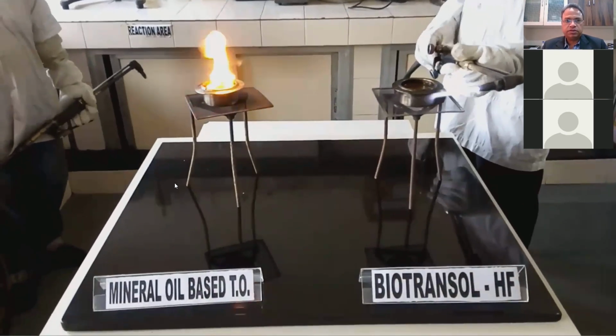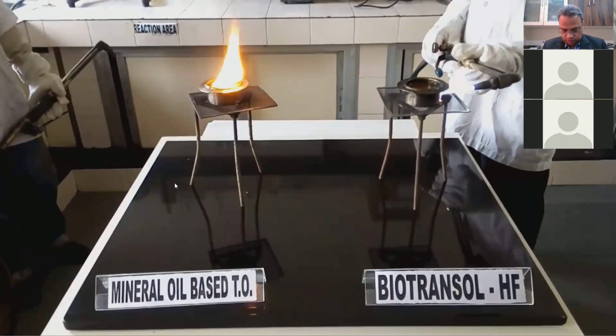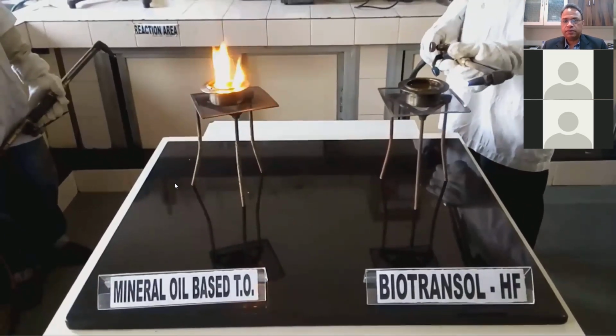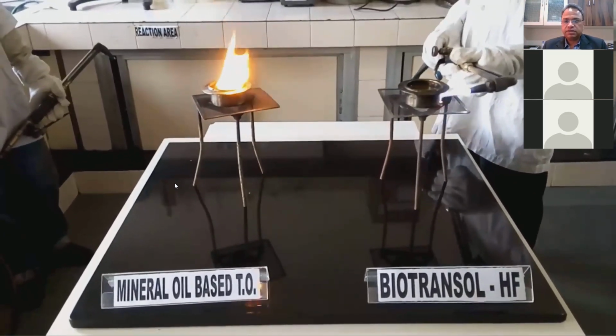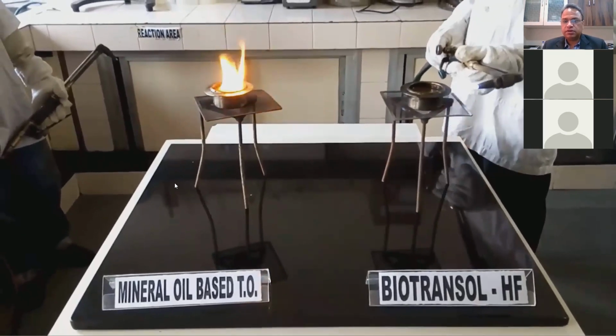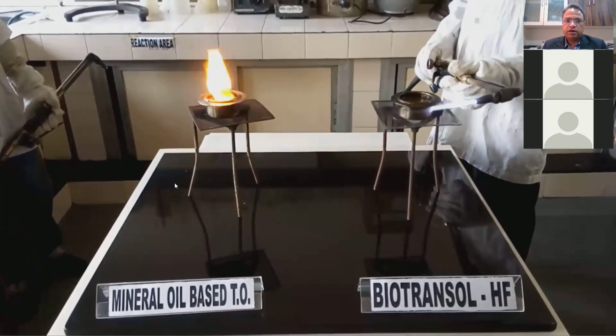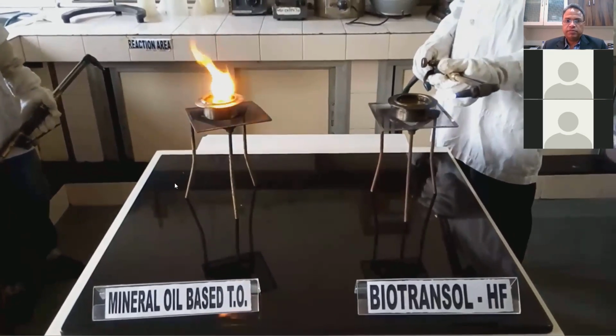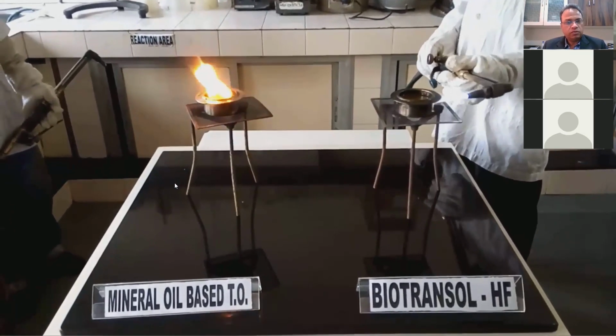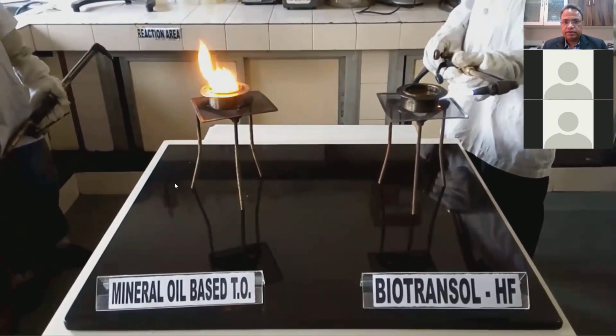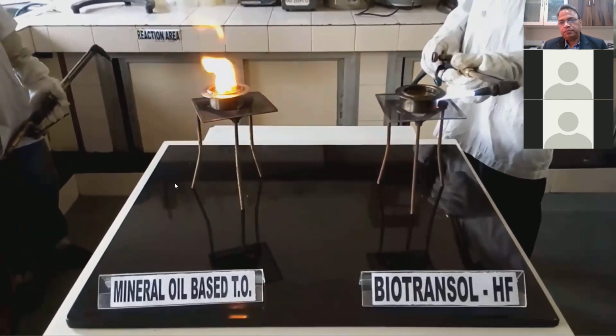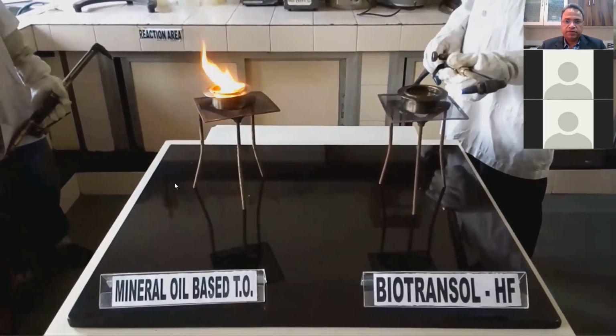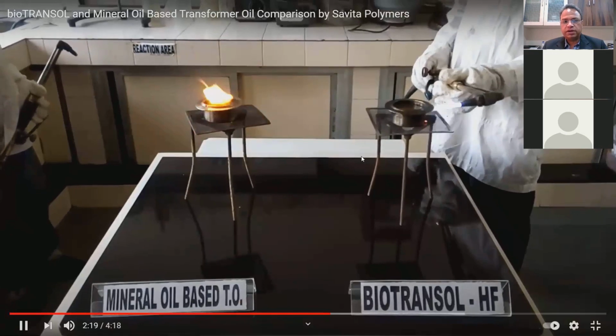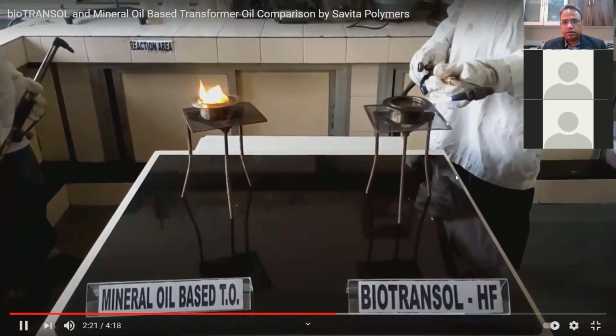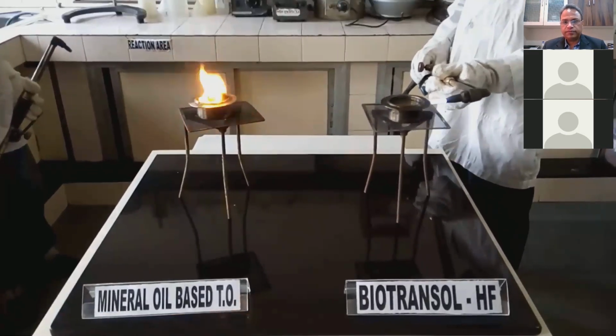So this is a demonstration of fire behavior of mineral oil versus natural ester oil. So you can see that the mineral oil transformer will keep on burning even if you are able to shut off the supply or shut off the load. An arc got quenched, but the fire will continue. So now you can see the smoke has started coming from this. It has started smoking.